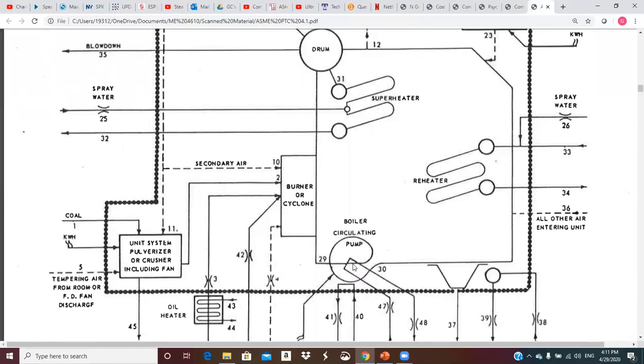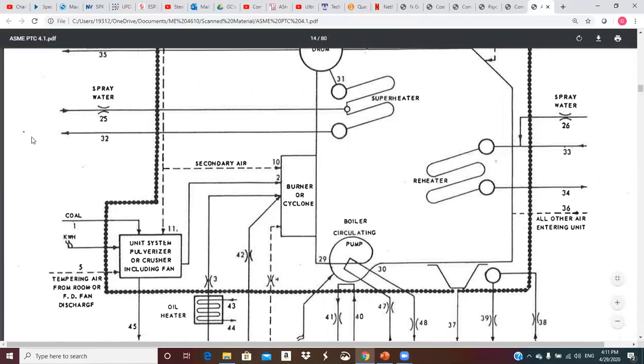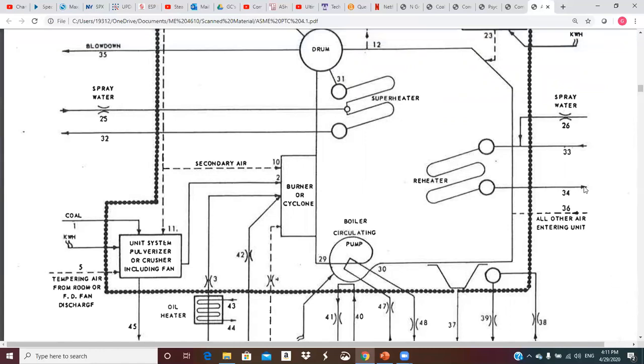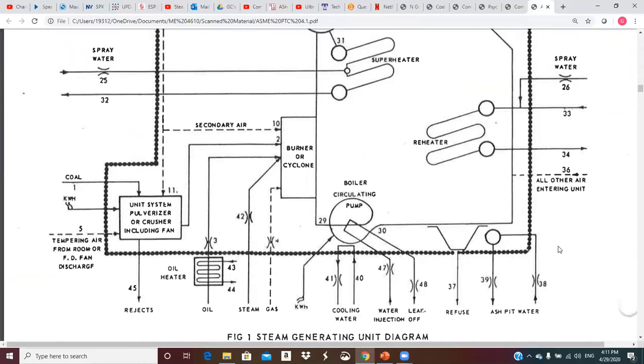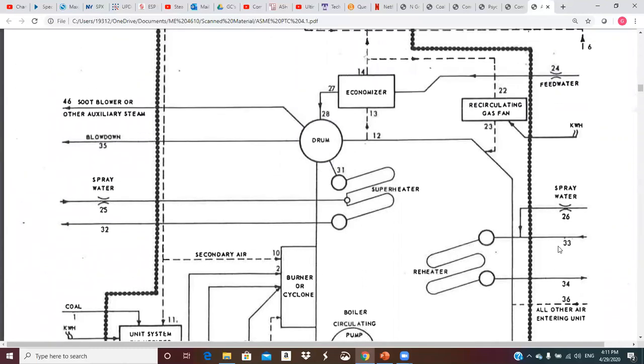So here is our reheat steam. So that steam goes out over here, goes through the high pressure turbine, comes out of the high pressure turbine, comes back over here for reheating. We have an attemperator here where we can spray into the cold reheat line. We go through the reheat superheater and then back out to the IP and LP turbines. Got a note here, 36, all other air entering the unit. Now we can look at the flue gas flow.